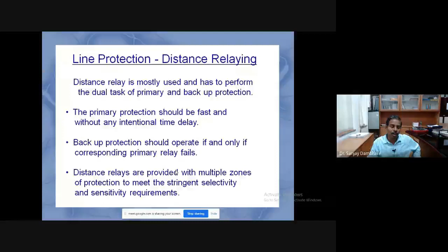And we know that for distance protection we have multiple zones, and zone 3 takes care of the remote end. There is a very wonderful paper on zone 3 setting by Professor Phadke, a critique on zone 3, and zone 3 should not be ignored, right? Because the reason for many cascading failures is zone 3, and zone 3 is as slow as possible. Sometimes people set zone 3 for 80-90 cycles. So it should take into account all possible conditions of the fault. This zone 1, zone 2, zone 3, we know how to set it. Normally for this line, 80% is set for zone 1, 120% for zone 2, and the longest line for zone 3. And this is the impedance mho relay. This is the transmission line characteristic, zone 1, zone 2, and zone 3.